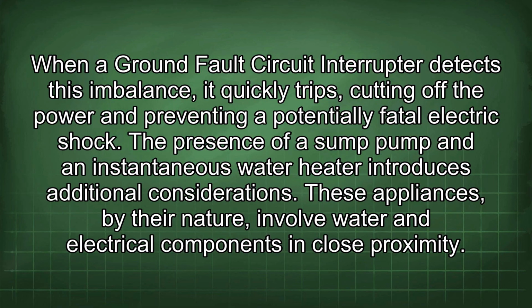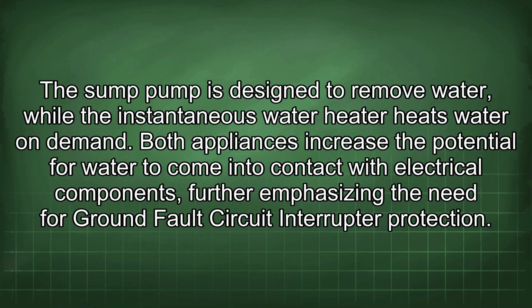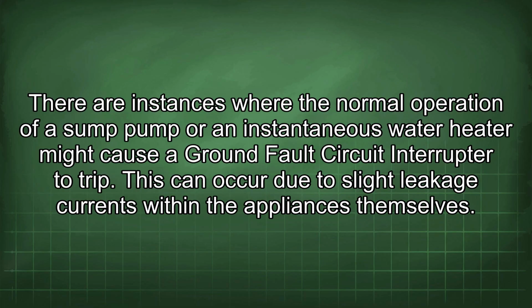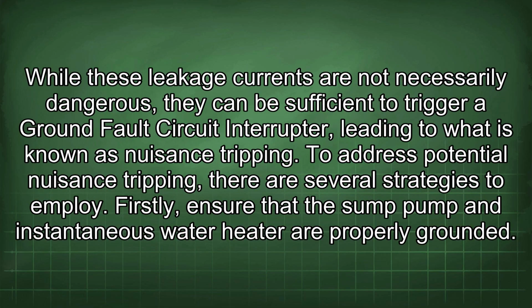The presence of a sump pump and an instantaneous water heater introduces additional considerations. These appliances, by their nature, involve water and electrical components in close proximity. The sump pump is designed to remove water, while the instantaneous water heater heats water on demand. Both appliances increase the potential for water to come into contact with electrical components, further emphasizing the need for ground fault circuit interrupter protection. There are instances where the normal operation of a sump pump or an instantaneous water heater might cause a ground fault circuit interrupter to trip. This can occur due to slight leakage currents within the appliances themselves. While these leakage currents are not necessarily dangerous, they can be sufficient to trigger a ground fault circuit interrupter, leading to what is known as nuisance tripping.